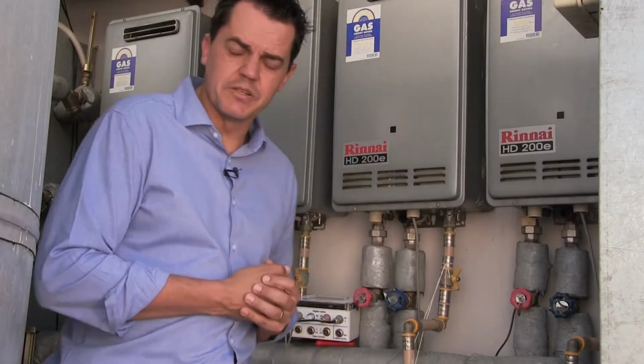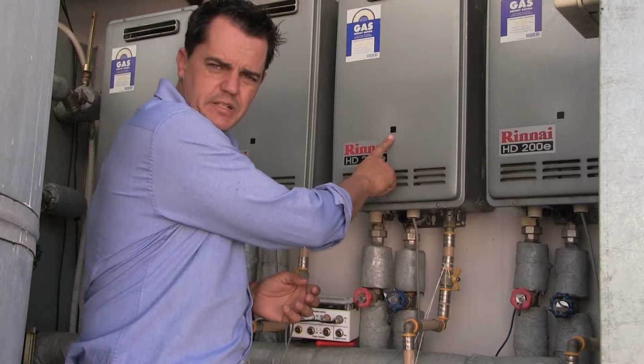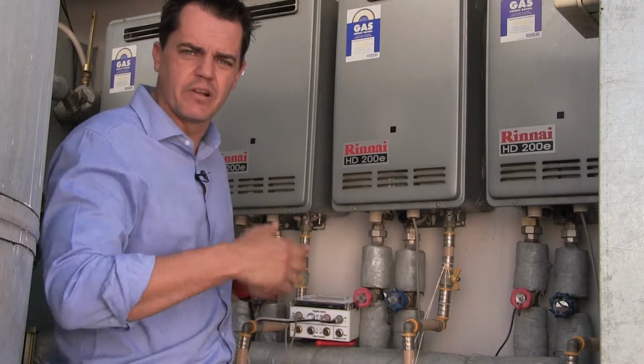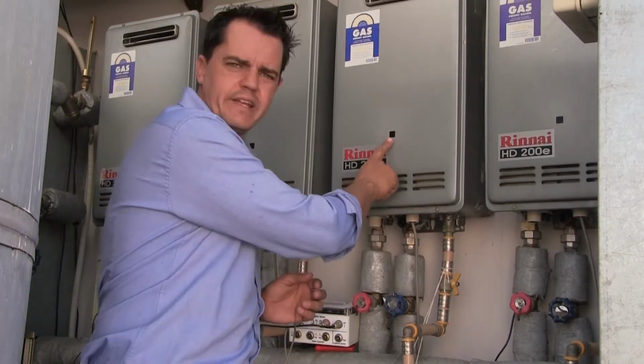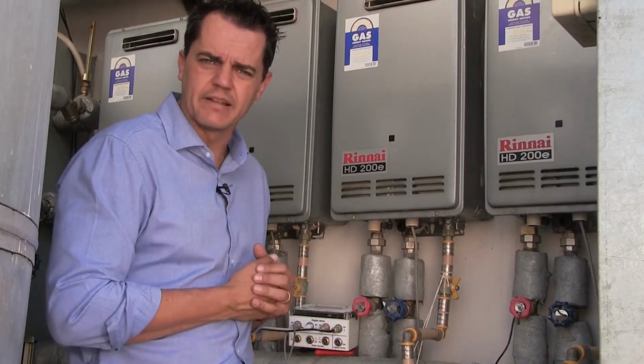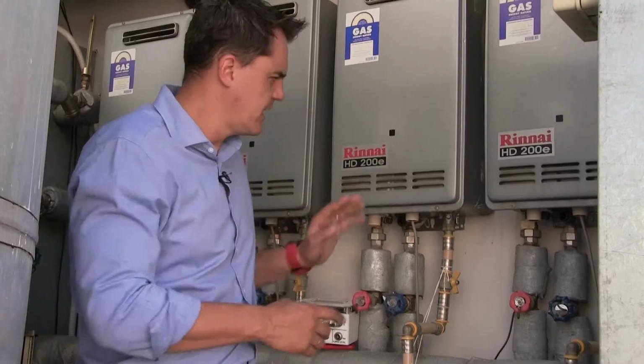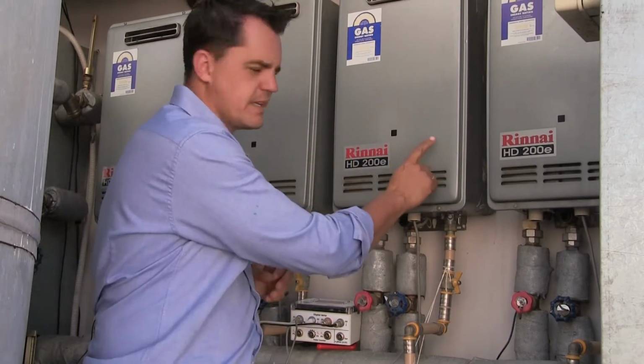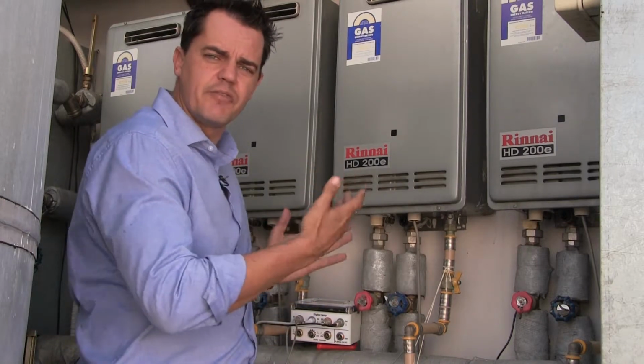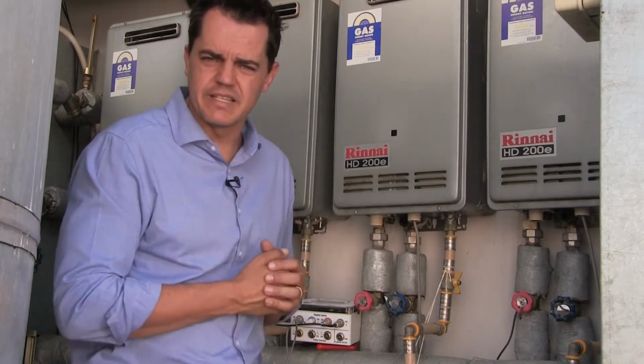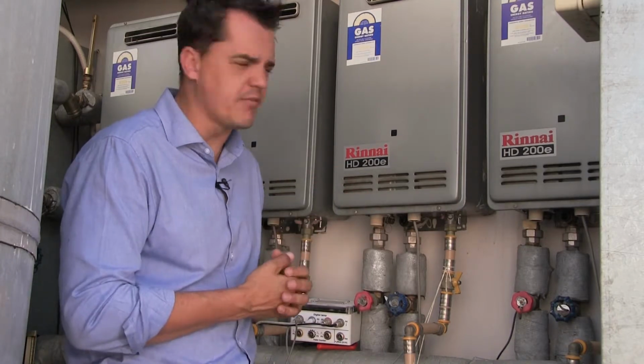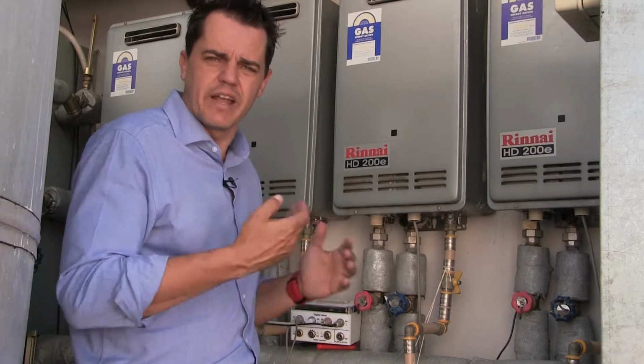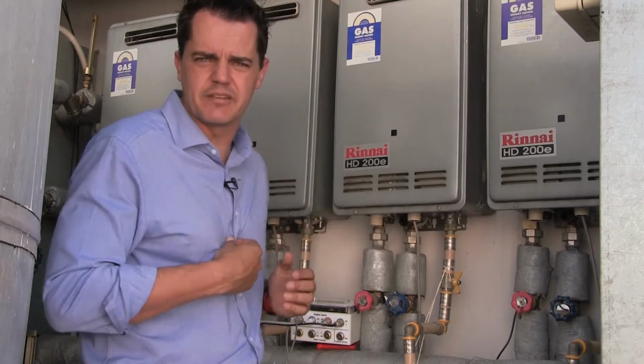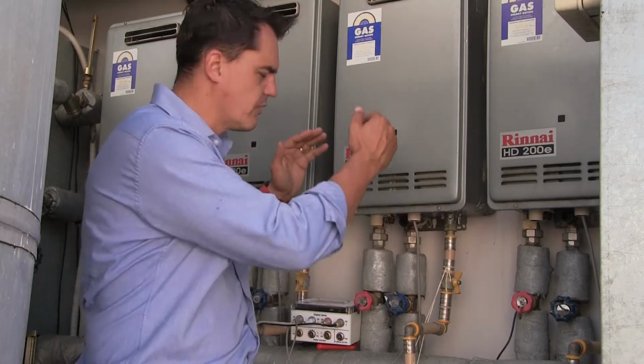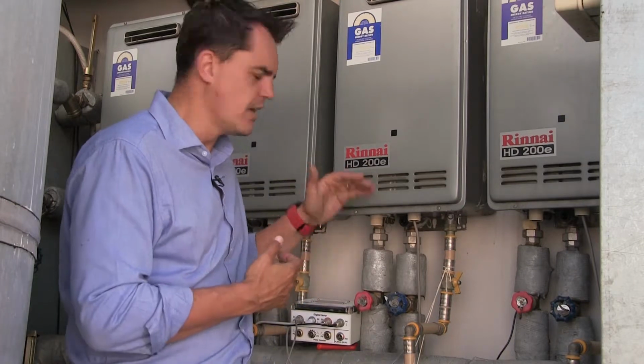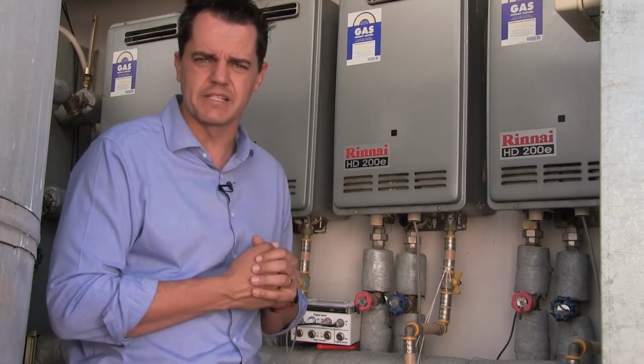When we look at the Rinnai burners in terms of error codes, all the error codes are displayed in this little window here. Under normal operation, if the Rinnai burners are functional and nothing is wrong, it will indicate the set temperature that it's heating the water at. Currently these units are set at 65 degrees. Inside this unit, if you take the cover off, there are little digits that you move from left to right. That then sets the temperature. So if it's set at 50 degrees or 55 or 60 or 65, you can take it right up to 85. The recommended temperature is about 60, maximum 65, because the higher the temperature setting, the more you reduce the life expectancy of the burners. So 60, 65 is ideal.